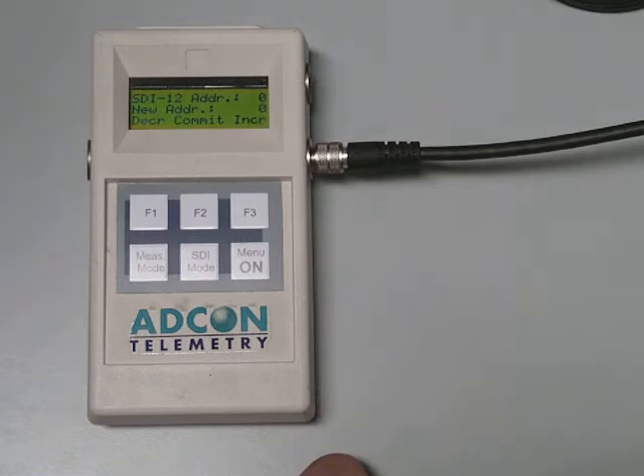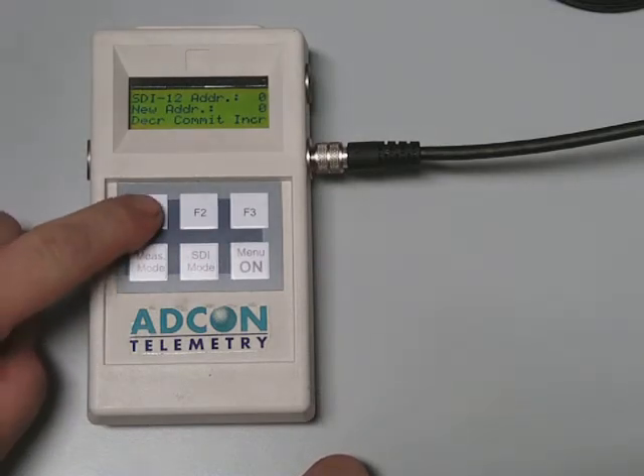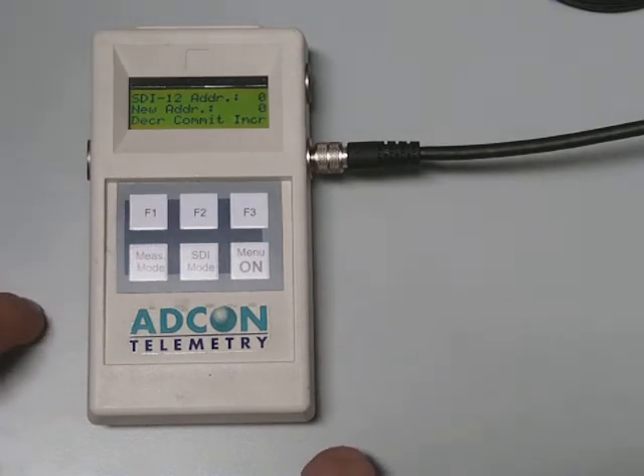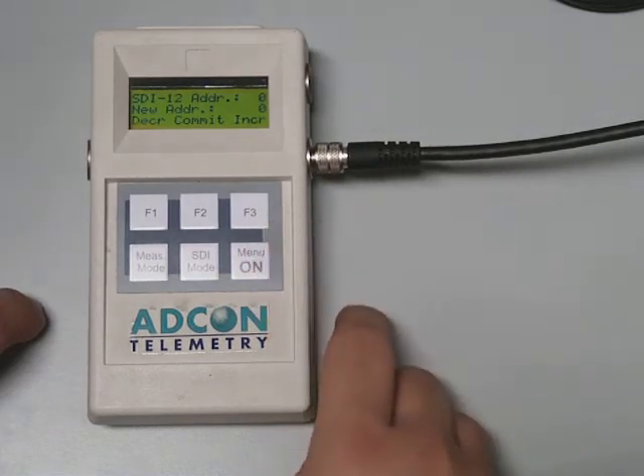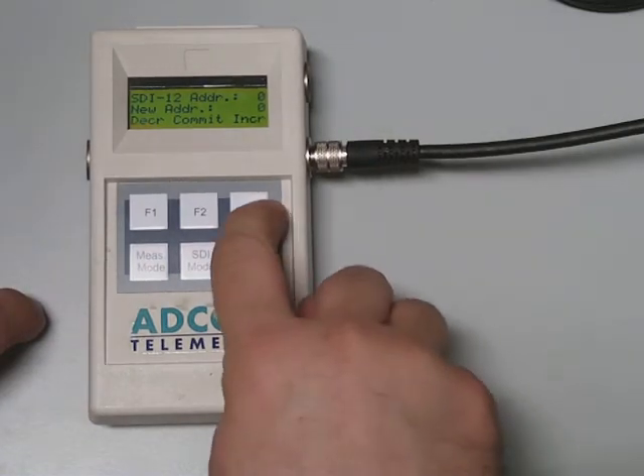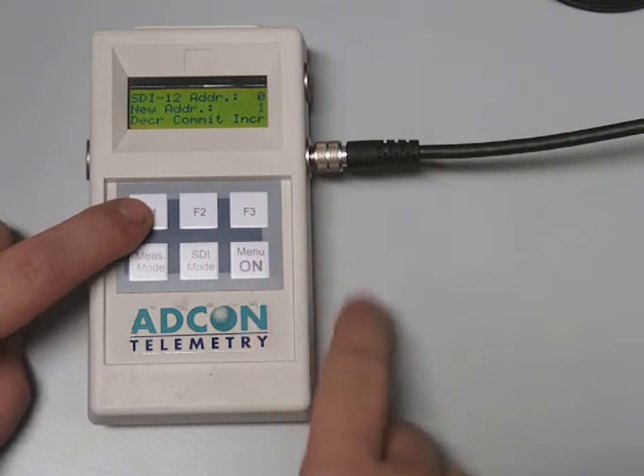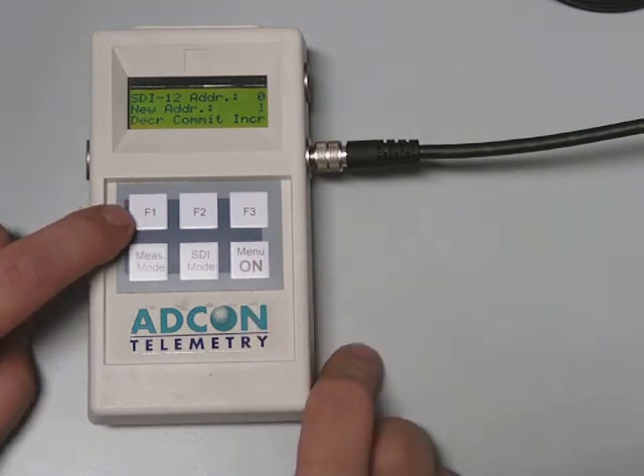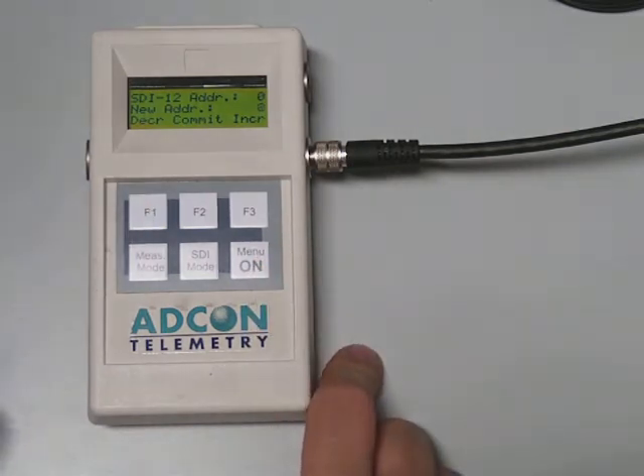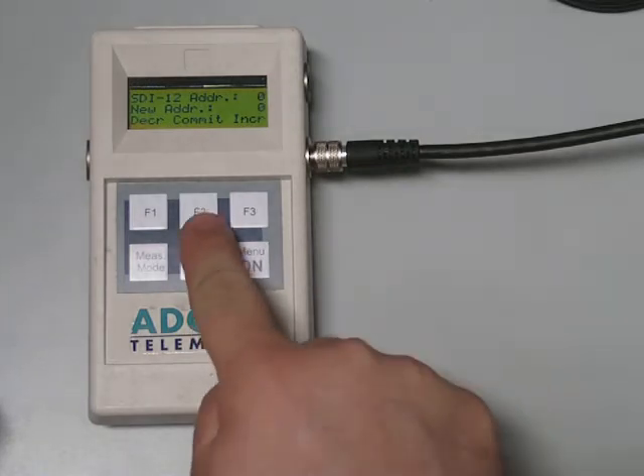Function number 1. If you push the F3 button or the F1 button, you can program a new SDI12 address into your sensor. Pushing F3 will increase the number by 1, pushing F1 will decrease it by 1. The second line of the display will show you the address you have selected. Once the correct address is being displayed, push the F2 button briefly to commit the new address.